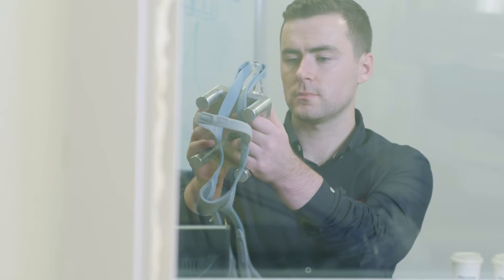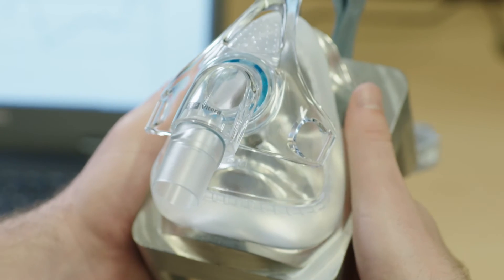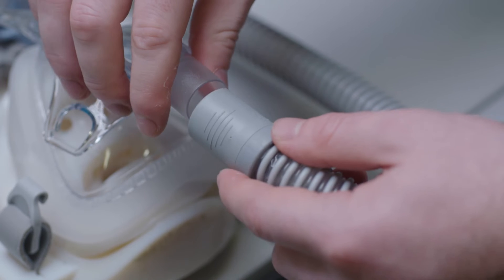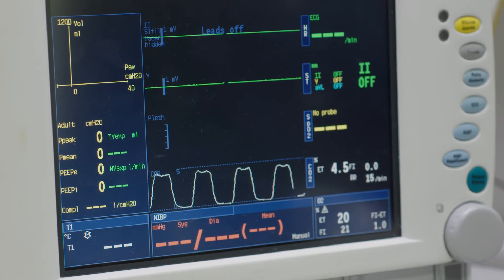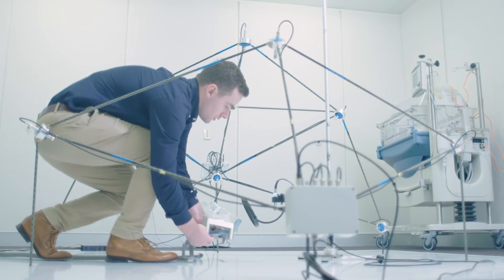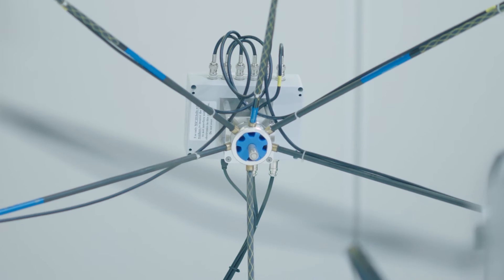I think we had 30 to 40 tests on Vitera just for that mask alone, making sure it meets our specifications, conditioning it, and then actually performing the tests. We test the level of CO2 in the mask during use. We test the sound output of the mask to make sure that it's not too loud in the room.